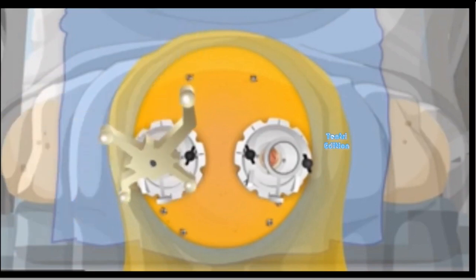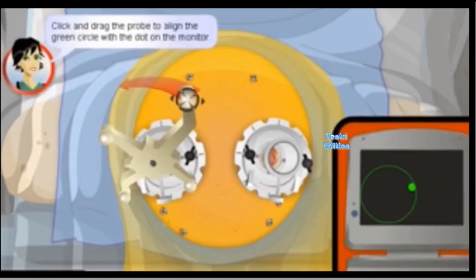Now, we want to make the final measurement of the fiducials and tower in relation to the computer scan. The error that the computer shows for all measurements has to be less than 1 millimeter for us to proceed. This makes absolutely certain that we are in the right place and will hit the right target when we insert the probes.